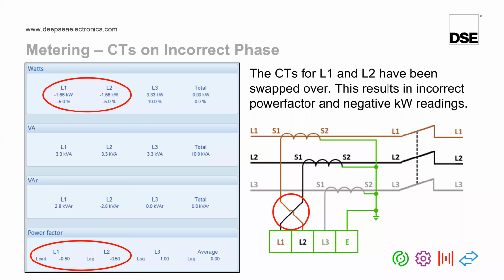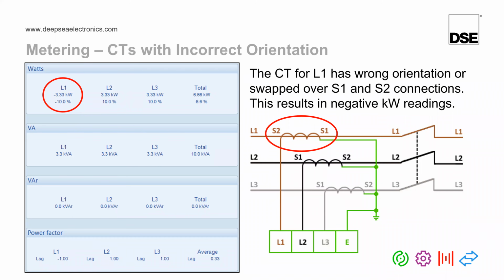So we first correct the power factor. If after we've corrected the power factor problem we still have negative kilowatt readings, this means S1 and S2 of the CT have been swapped over, or the physical orientation of the CT is wrong. You can see here L1 is showing negative kilowatts, when in actual fact it should be positive kilowatts. You can't always rely on the stickers or the indications or markings on the CT. Many times we have at DSE come across CTs with plastic cases or stickers that are wrong because the iron core and the windings inside have been connected incorrectly. So this test will always prove if the DSE module is measuring kilowatts correctly.